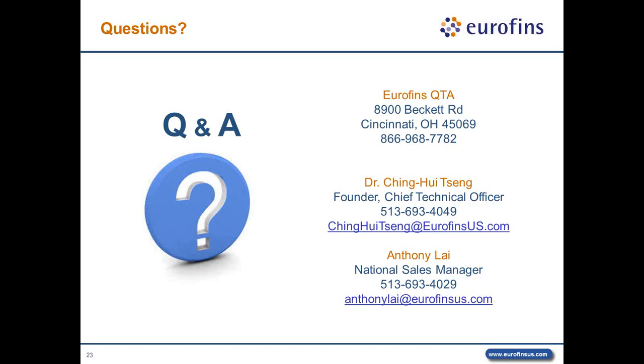That range is really what will allow us to have everything that we need in terms of samples and data to give you some performance indicators of how well this is going to work for each given parameter that you'd like to test for. If we got 20 samples that are all right on top of one another, all we're really telling you is that we're able to identify a given number that's static, where what we want to be able to do is show you how well it can predict values across a range, and when that gets outside of the range that you're comfortable with or that you're expecting to see. So that's probably the biggest time factor, the collection of those samples over the range.